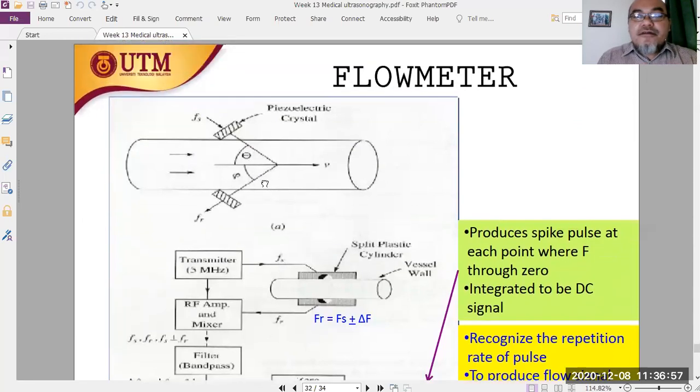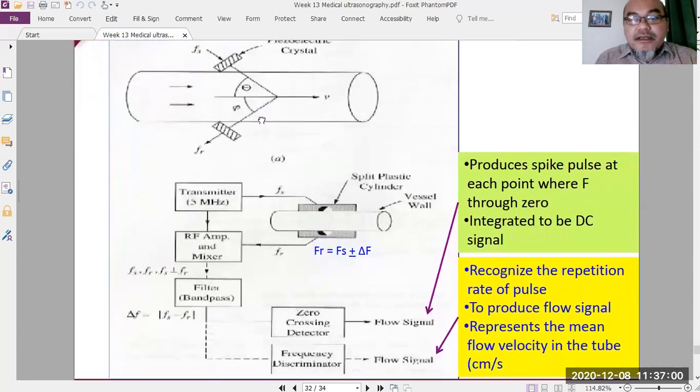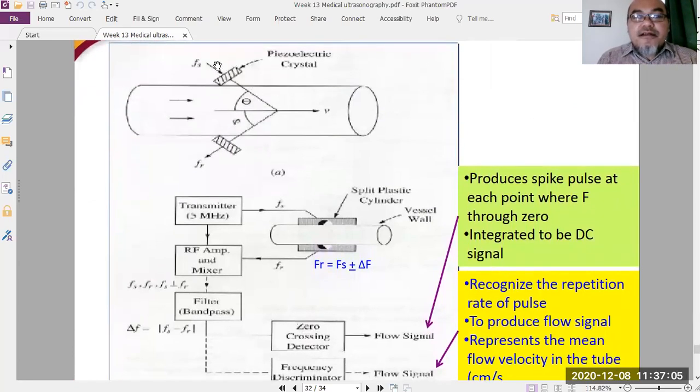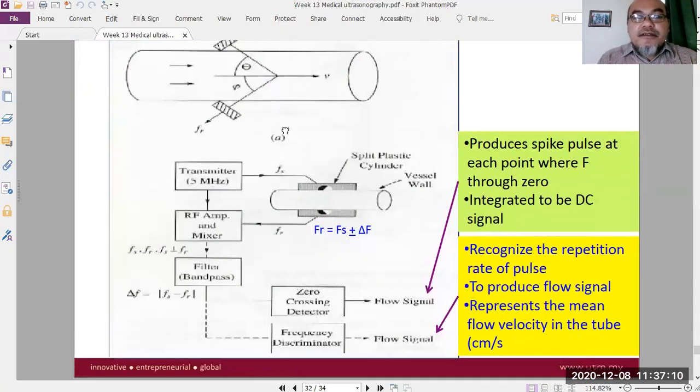So this is how it looks if we use a Doppler flow meter. This is the piezoelectric crystal transmitting the wave, and this is another piezoelectric crystal receiving the wave. The transmitter here at 5 megahertz is in the vessel wall, and the receiver will receive the frequency with plus or minus delta F, which is a function of the flow rate inside that vessel.